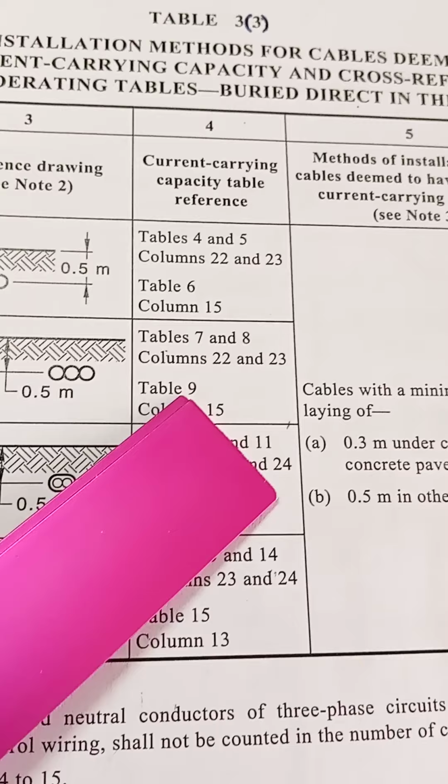So what I want to do is just break it down. The two types of cables that we can get are either two core or, sorry, two single core, three single core cables, two core cable, or three core cable. We don't see four core cables because the neutral and the earth don't take effect. It basically says here earthing conductors and lightly loaded neutral conductors of three-phase circuits and so on. Basically they're saying they're not counted.